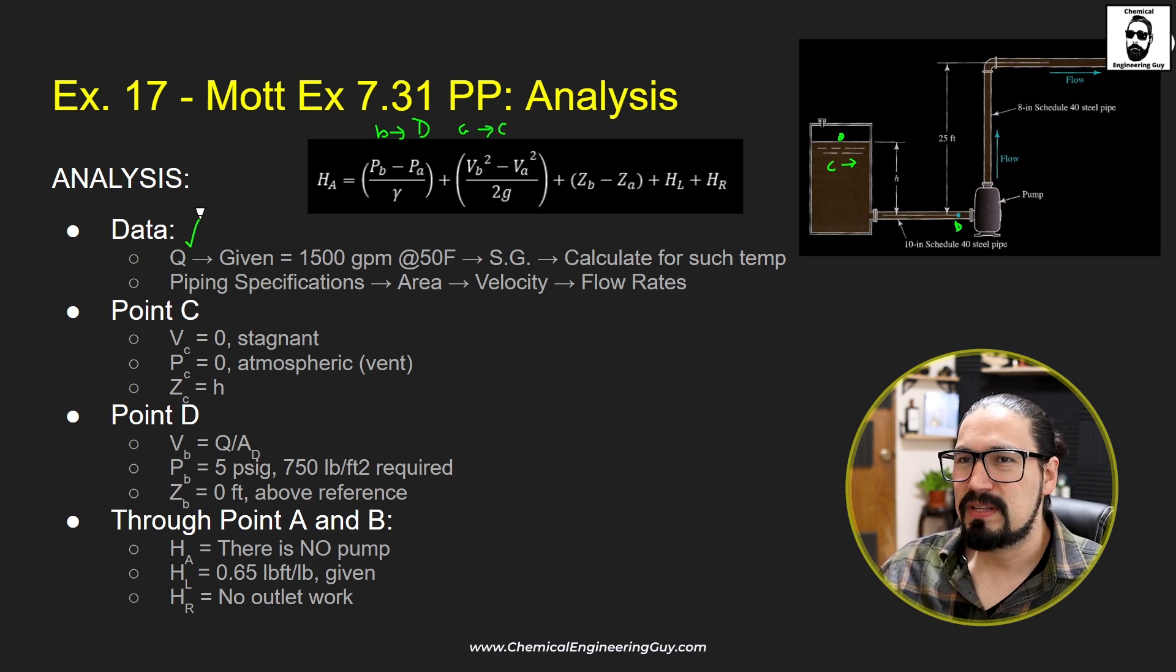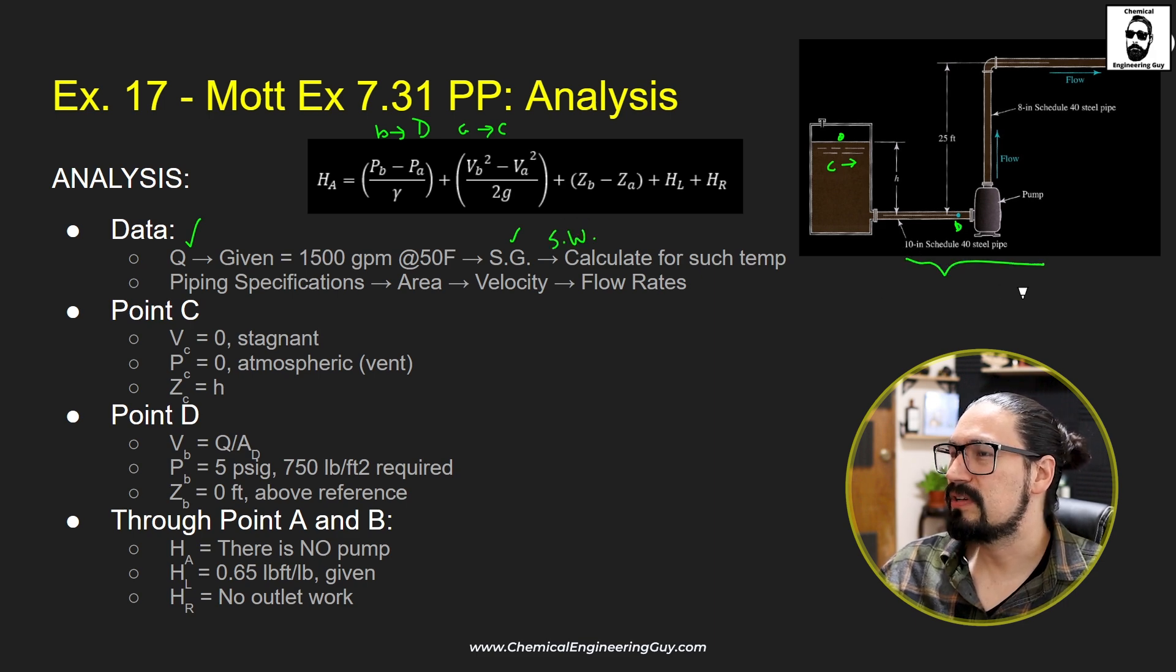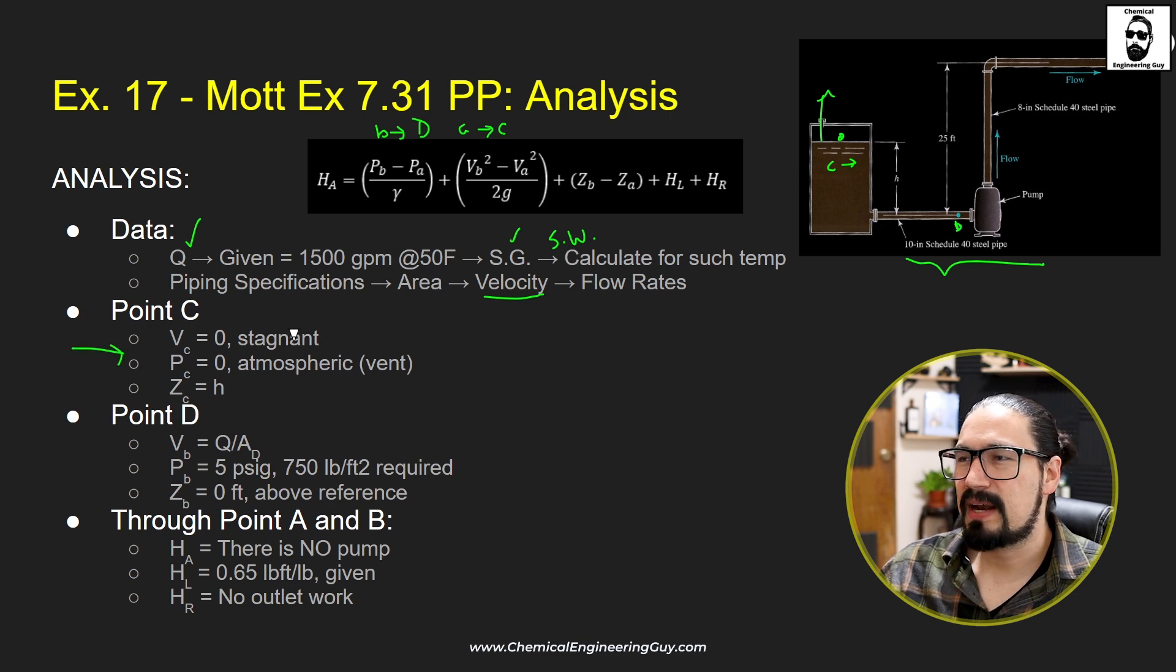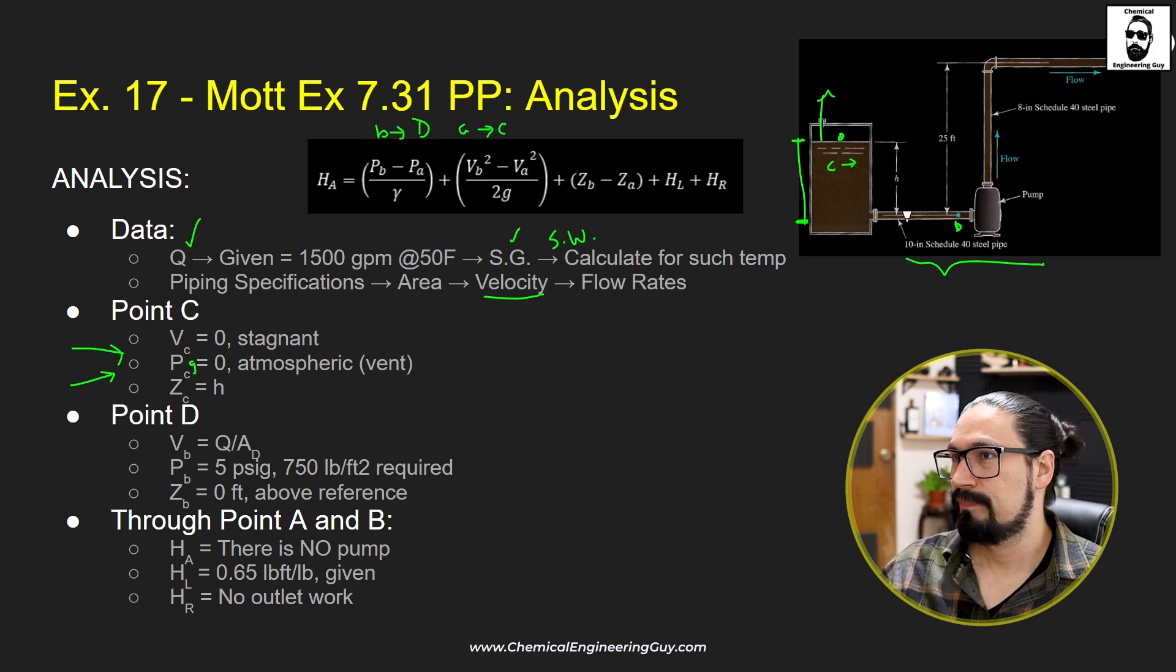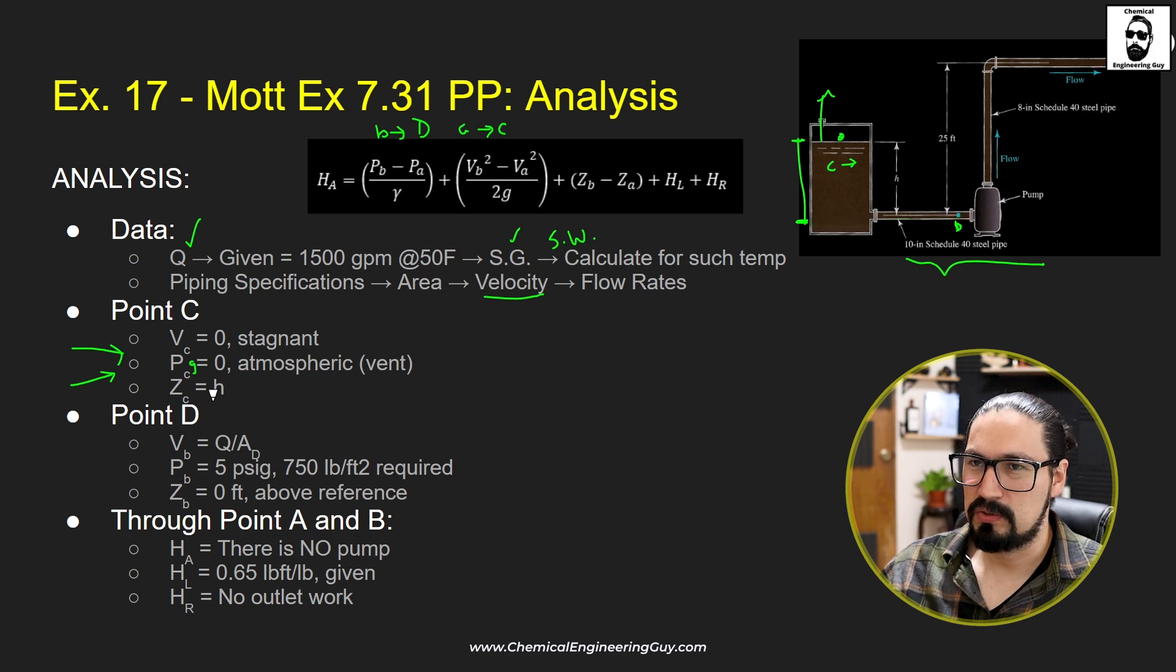Volumetric flow rate is given. With temperature we know the substance and can calculate the specific gravity and specific weight of water. We know the piping specification is a 10 inch diameter schedule 40 steel pipe. From point C, you can see that this is open to the air, so this is a vent. Velocity in a tank will be stagnant, so velocity is zero. Pressure will be zero because I'm going to be using gauge. The height I don't know, but I want to make the reference value the point of the suction line. This is H.